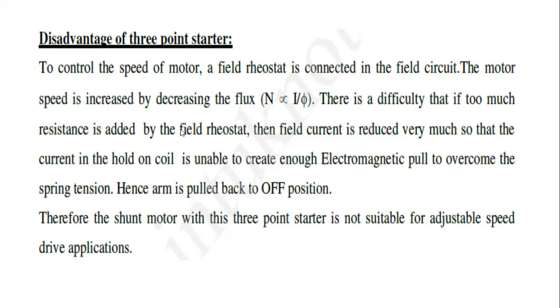If the field rheostat is added, there is a difficulty because resistance is added for controlling the field. We are increasing the n number of resistances, and then it is a very difficult process. To overcome that difficult process, we are using another type of starter. Therefore, the 3-point starter is not suitable for adjusting the speed of motors.